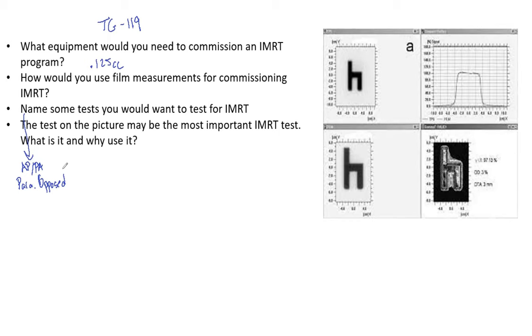Then move up to a multi-target: for example, three cylinders of increasing dose, seven fields placed 50 degrees apart, a chamber at isocenter, and film to analyze other segments at mid-phantom. TG-119 gives recommendations but you can make plans a little easier or more complex as you see fit — you have creativity as a physicist to come up with your own plans.